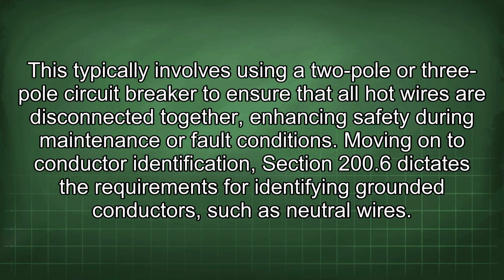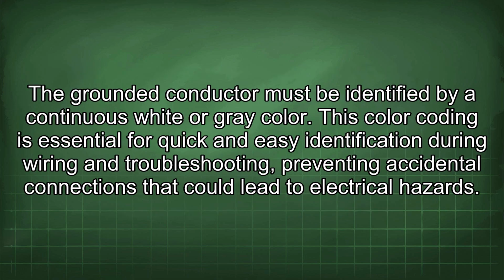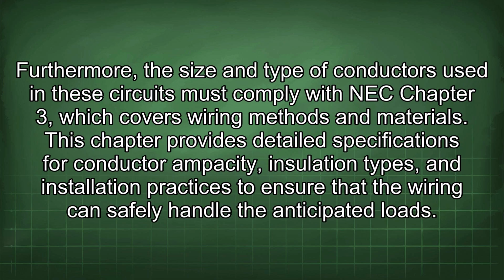Moving on to conductor identification, Section 200.6 dictates the requirements for identifying grounded conductors, such as neutral wires. The grounded conductor must be identified by a continuous white or gray color. This color coding is essential for quick and easy identification during wiring and troubleshooting, preventing accidental connections that could lead to electrical hazards. Furthermore, the size and type of conductors used in these circuits must comply with NEC Chapter 3, which covers wiring methods and materials.